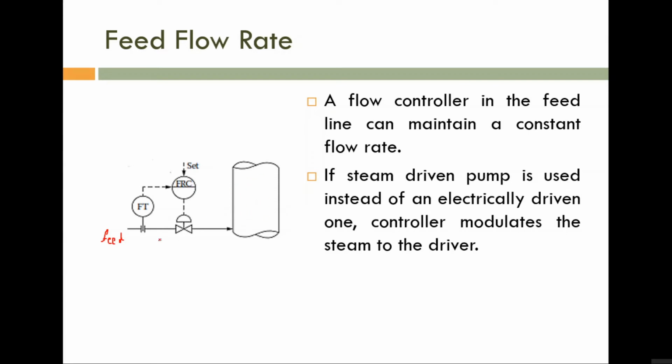If it is a first distillation tower, this feed is pumped by either a steam driven pump or an electrically driven pump, means electric pump or steam pump, from some source. Okay, so please note here the flow rate of this feed is measured. Okay, so this one is a measurement. By using this measurement, FRC is manipulating the same feed flow rate. So here the controlled variable and manipulated variable are both the same. Okay, so please note the feed flow rate is measured, and by using that feed flow rate, the FRC is manipulating the same feed flow rate.